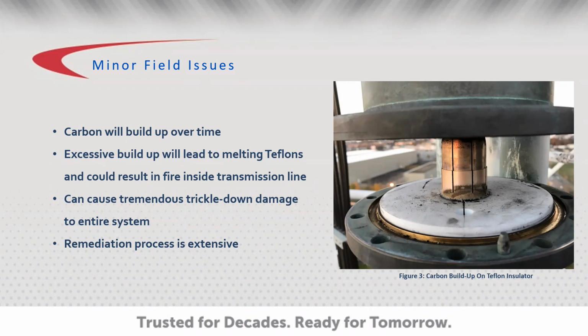These events can cause significant damage to the entire system and are not localized to a particular area. The remediation process is both extensive and costly. It consists of breaking each joint, sweeping off debris, cleaning the Teflon with denatured alcohol, and then connecting the flanges again. This process would need to continue from the point of interest downward to ensure that all of the debris was removed.